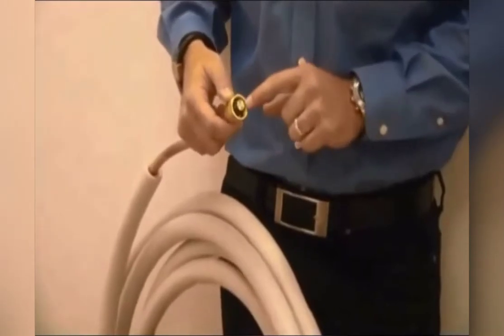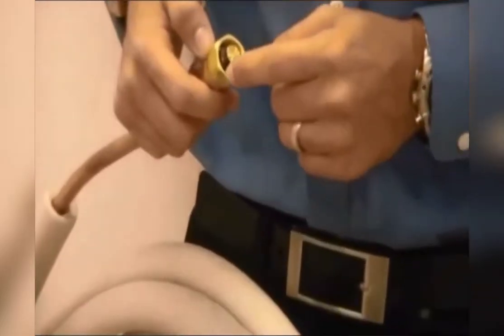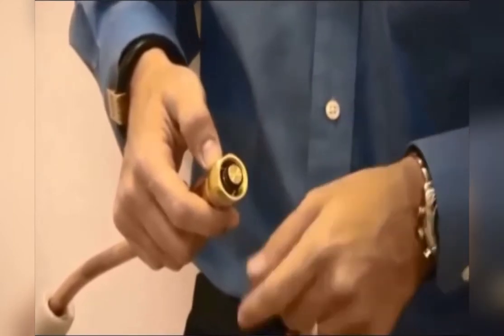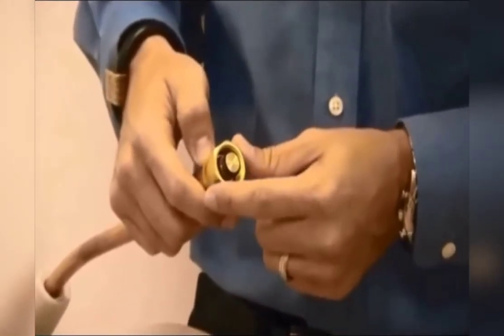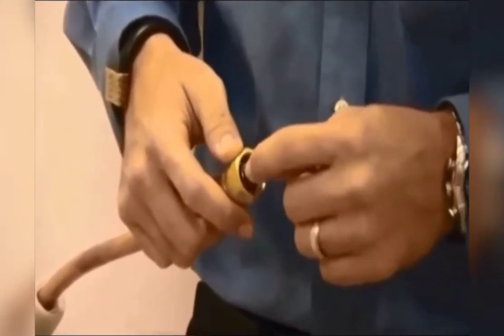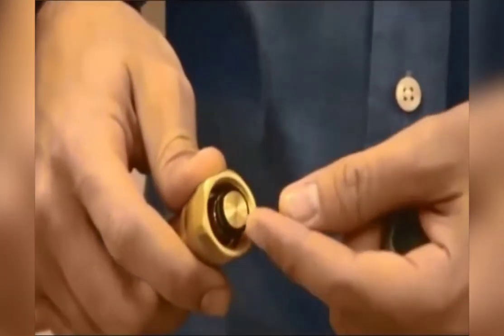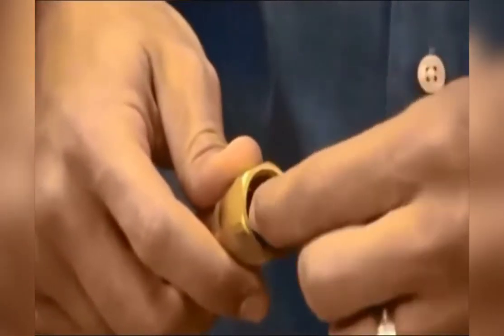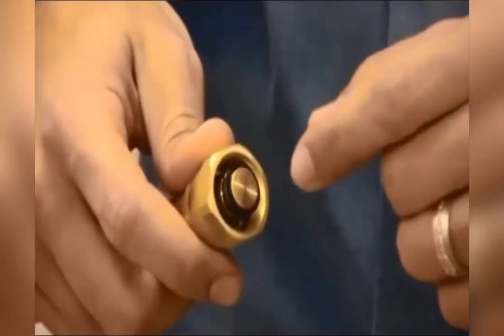First, inspect your threads and ensure that they're clean and undamaged to prevent any cross-threading when installing. Second, you want to inspect the O-ring sitting in this area. You want to ensure that it is sitting flat on the space and ensure it's not damaged to prevent any future leaks within the system.